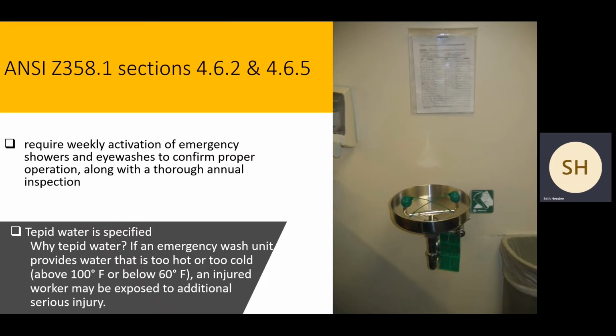So the ANSI document Z358, sections 4.6.2 and 4.6.5, talk about eye washes, and require weekly activation of emergency shower and eye wash to confirm proper operation, along with a thorough annual inspection. Tepid water is specified. So why tepid? Well, in an emergency, the unit should provide water that's not too hot or too cold. You may have to flush your eyes for 15 minutes. And if something is too hot or too cold, of course you're not going to be able to keep it in there.